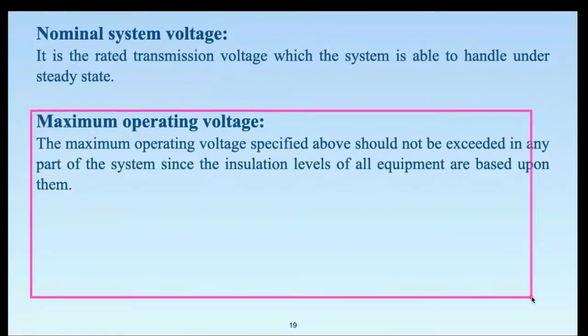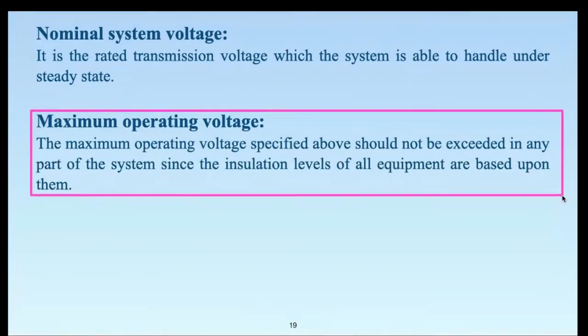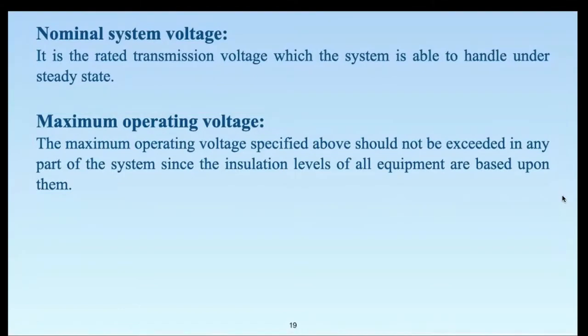The maximum operating voltage is the voltage specified in the list and it should not be exceeded in any part of the system. This is the voltage level on which the insulation level of all equipment is based. The relation between maximum operating voltage and nominal system voltage varies — it may be up to 10 percent higher at 132 kV, and around two to three percent higher at the voltage level of 750 to 765 kV.